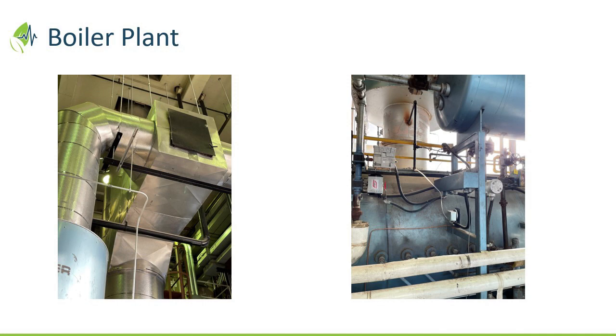Whether it's a coil tube, water tube, or fire tube, it's a heat exchanger. And so in any of those instances, there's two sides for a failure mode. There's the water side, so you need flow, and you need a clean flow path. So if you start building up scale, all your heat energy is going to the exchanger and will create a failure on any boiler type. On the flue side, if you start sooting up, so you start creating carbon on the outside of that, once again, you're insulating the tube, you're overheating it, you will fail. In the instance of a water tube, forced circulation or traditional, you can freeze them because you have high heat transfer values. So if you get that downdrafting, you can absolutely freeze and split the coils. But those are your primary failure modes. So you need to keep the water clean and the combustion clean.